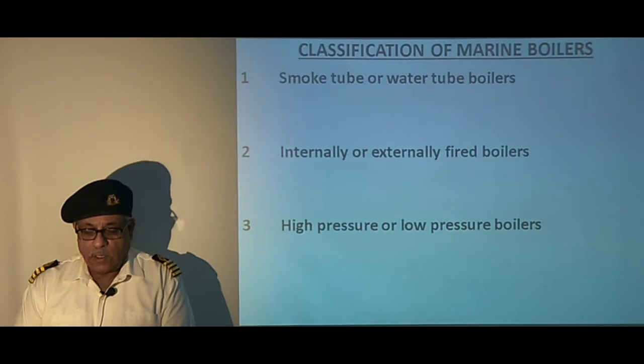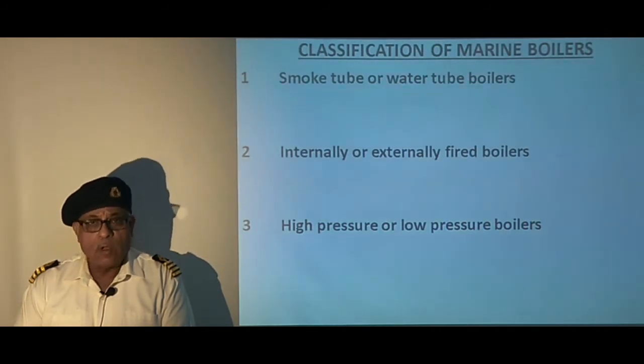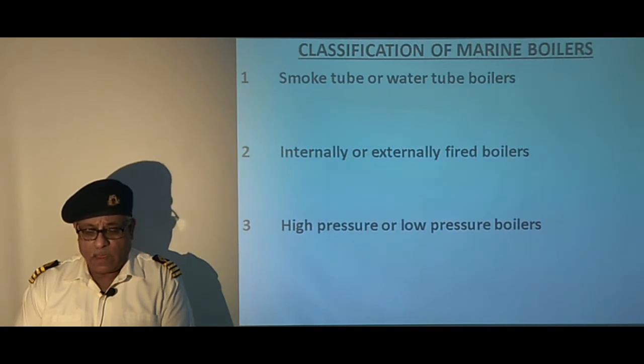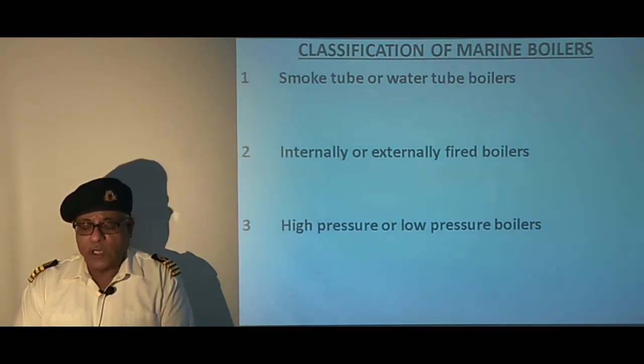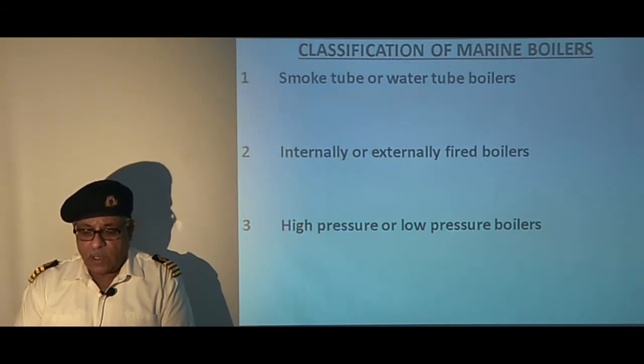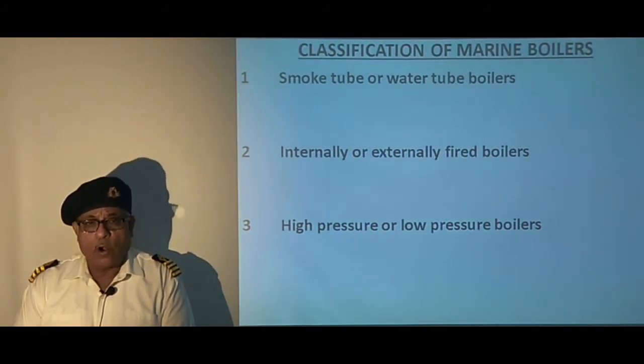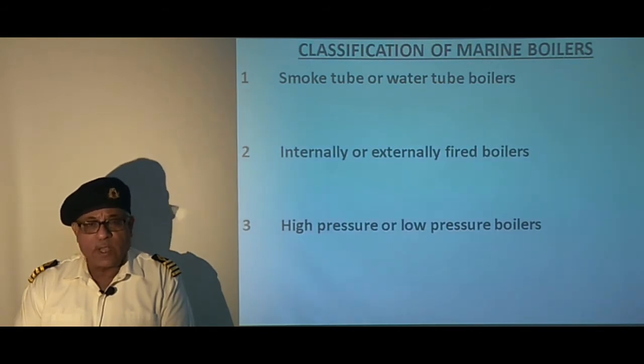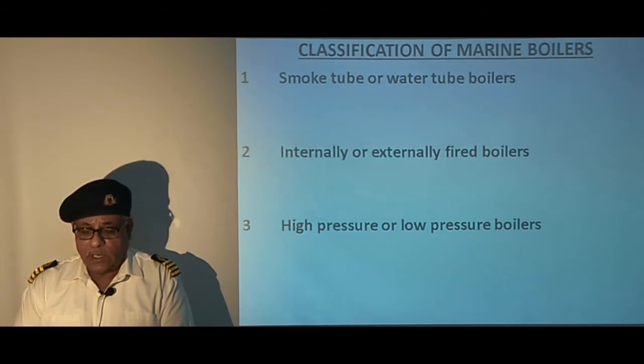Third is classification on the basis of boiler pressure. Boilers below 32 bar pressure are called low pressure boilers and above 32 bar are called high pressure boilers. Steam ships are equipped with high pressure boilers whereas motor vessels use low pressure boilers.